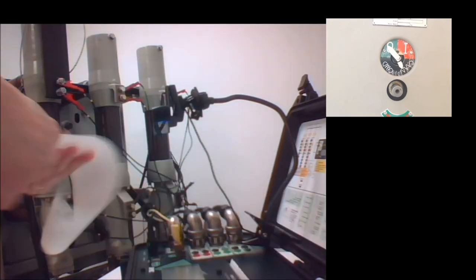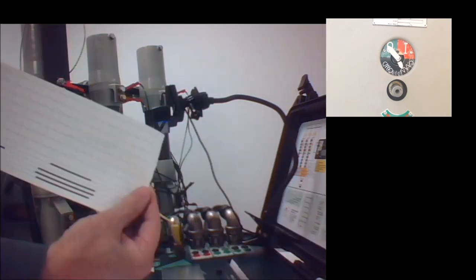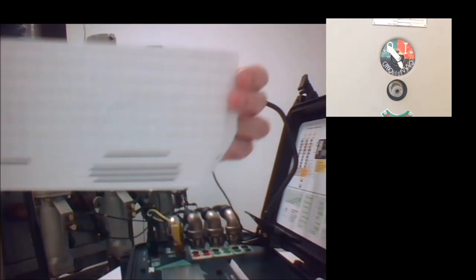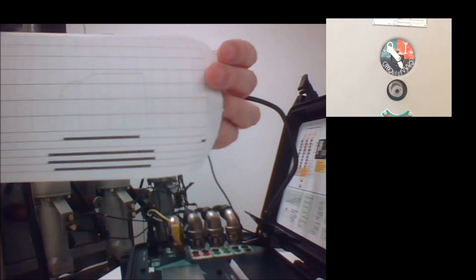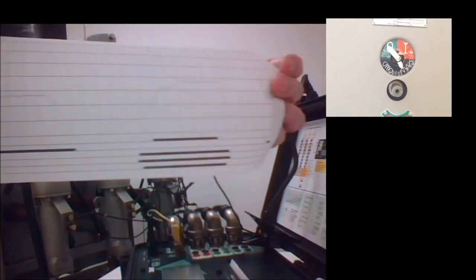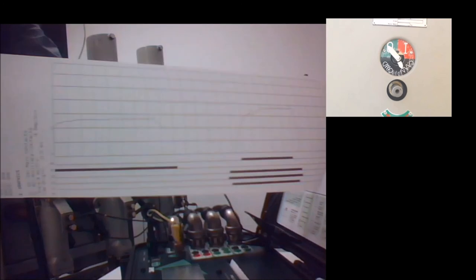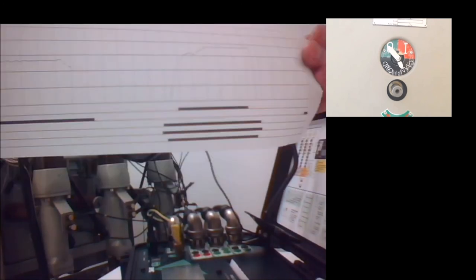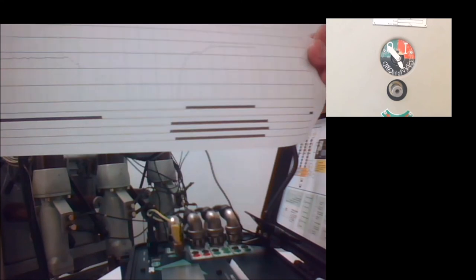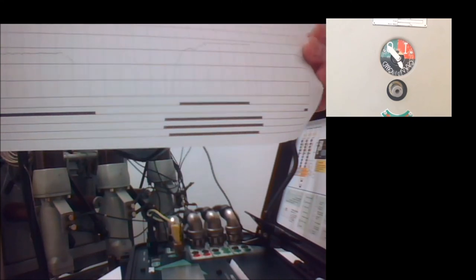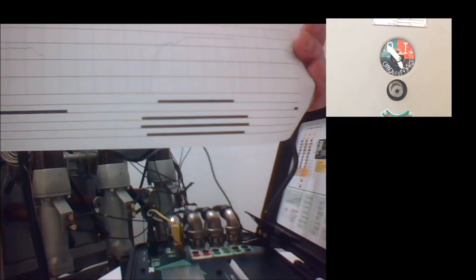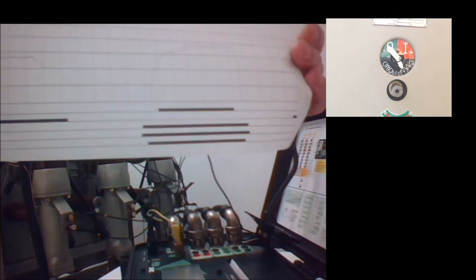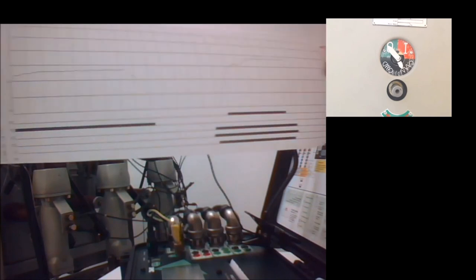Coming back to the results, you can now see three values for the contact resistance: 0.216 milliohms for the first phase, 84 micro-ohms for the second phase, and 94 micro-ohms for the third phase. These are quite different values — intentionally so, because this is a breaker used for training. We can see more details about the timing of the main contacts, the three main contacts, and two auxiliary contacts also connected to the instrument.